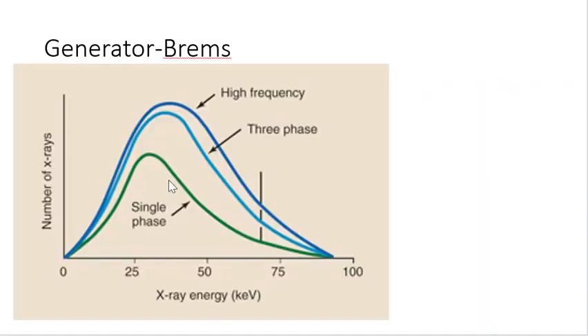Here are the effects on the Bremsstrahlung spectrum. Going from single-phase to three-phase, the peak of the curve representing average energy shifts toward the high-energy side and the height increases, indicating greater output. Going from three-phase to high frequency, the same pattern continues — the peak shifts further toward high energy and output increases slightly.